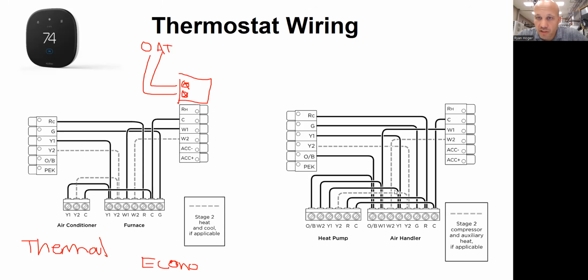So Gary, following up on our previous question, says we need a thermostat designed for heat pumps. Usually the answer to that is yes. There's some slight exceptions, but almost all the time you will need a heat pump thermostat. Specifically, you need one that has an OB output on it. Your existing thermostat might have that. It might not. Depends on what your existing stat is.